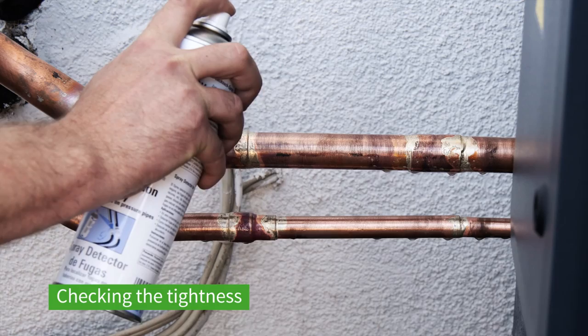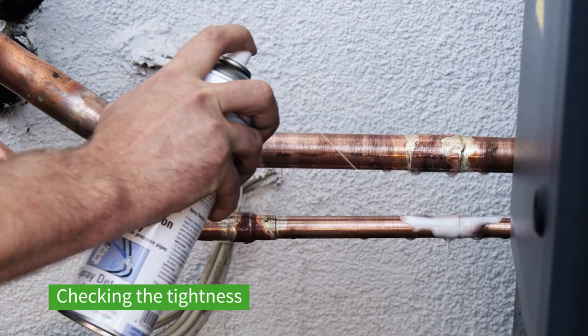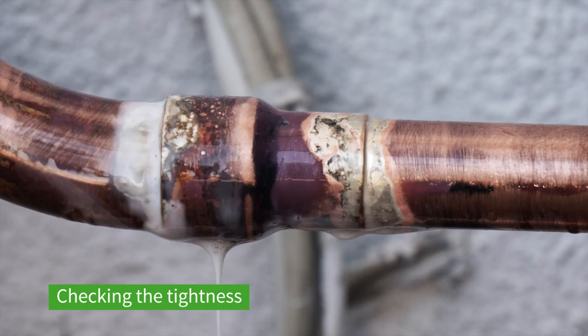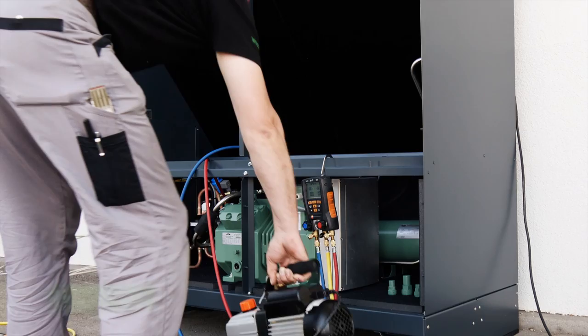Once all the refrigeration system components have been mounted, check for leaks with dehydrated nitrogen. A pressure level test should be carried out in sufficient time. Ensure the maximum allowable operating pressure.